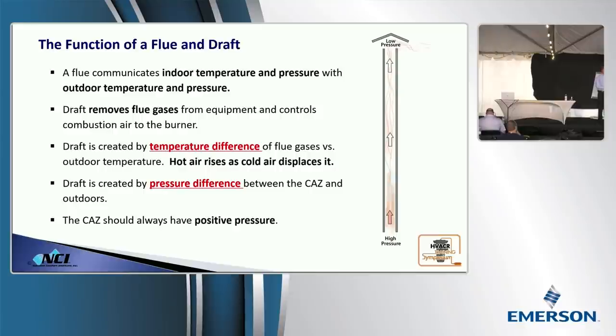Everybody says pressure. If pressure is what affected draft the most, we'd all be dead. If we ever stopped in a mechanical room, we would be dead. Temperature is the number one driver on draft. The heat of the flue gases is what creates that flow. Those that are familiar, we're going to talk about stack effect in a little bit. Stack effect is an old school term for flue. So you could also think of stack effect as flue effect. And this is where we start to tie the building as being part of a duct system in. Temperature is a big driver when it comes to flue draft. So this is why it's so important that the equipment that you guys install is fired correctly. If we underfire it, the flue gases are really cool, we don't get a lot of draft.